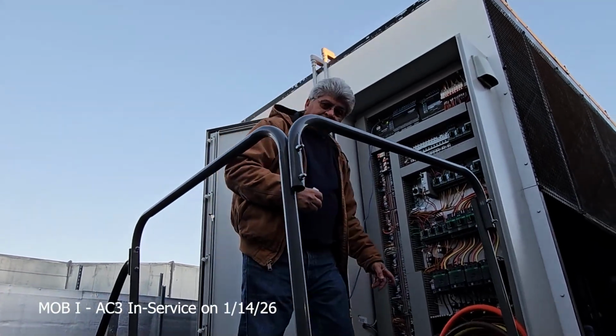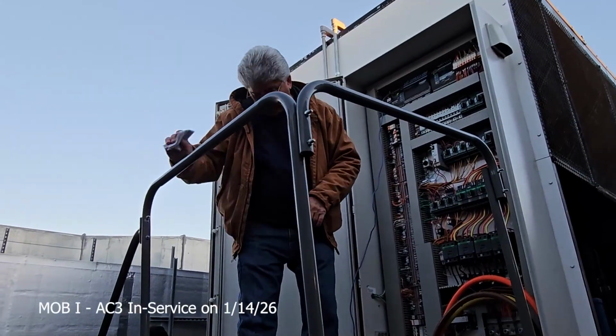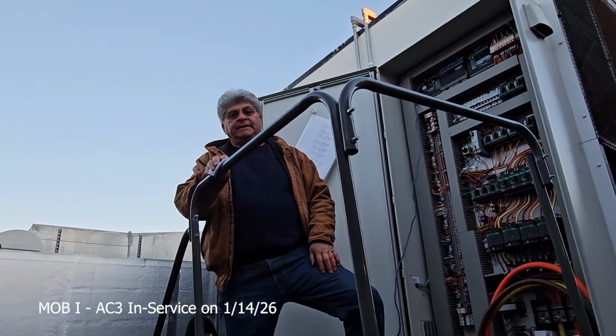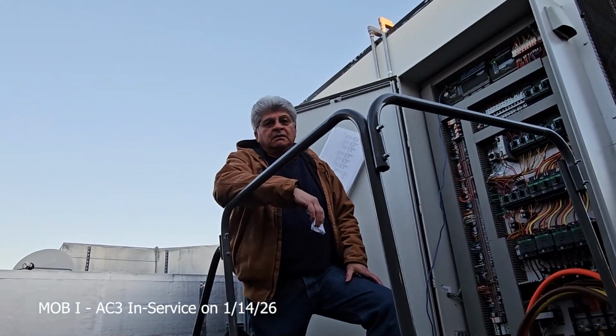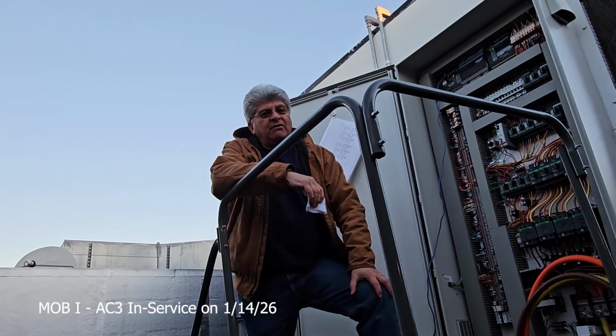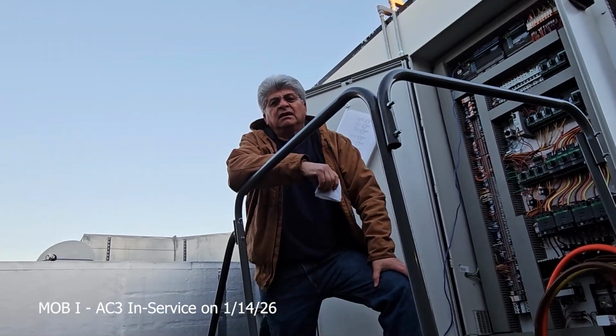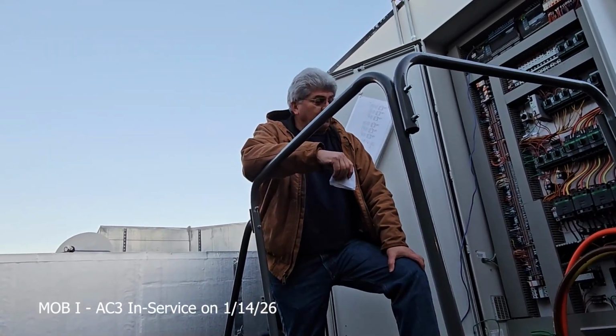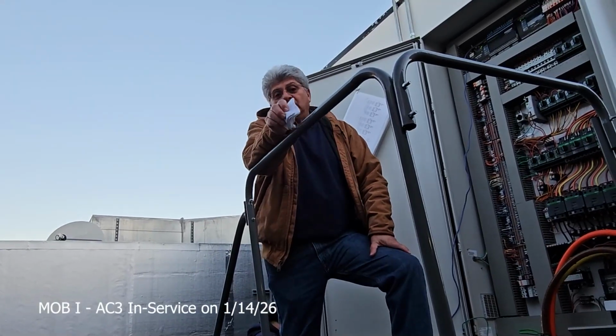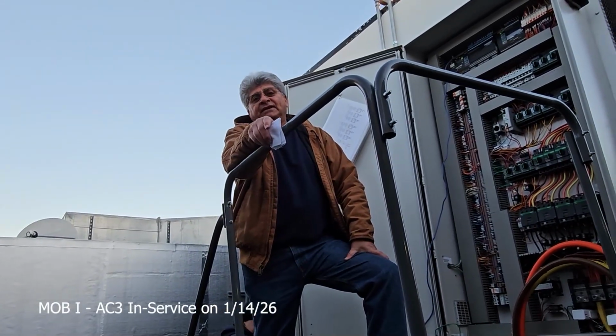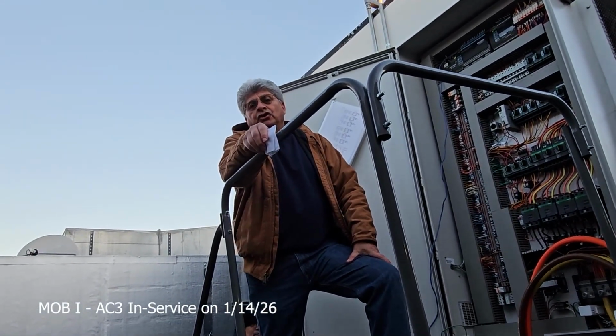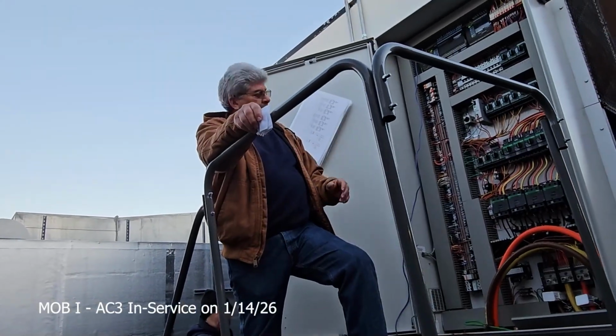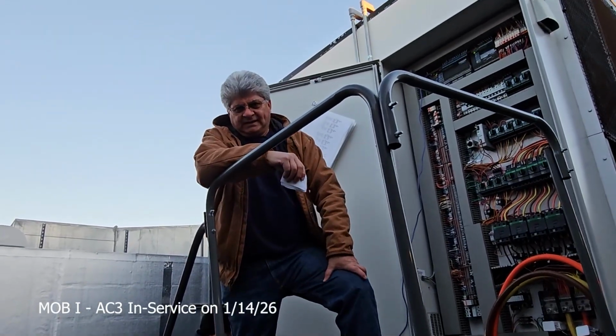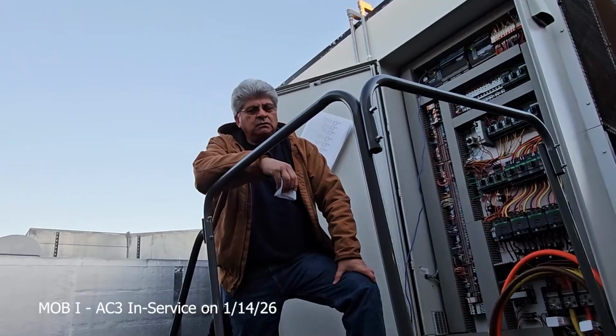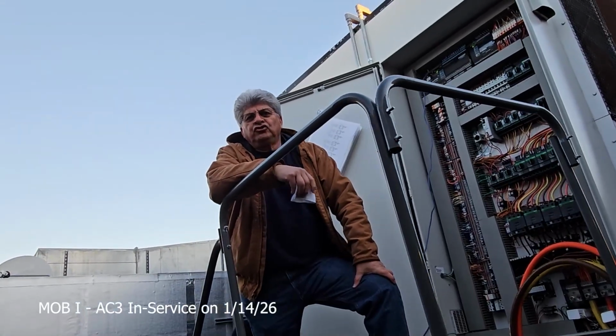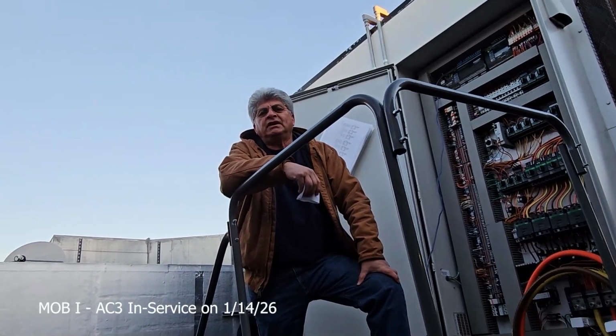Does it have the Delta P alarm trip? I'm not a smart guy. What's a Delta P? The filter dirty. Oh, static pressure alarm. Yeah, static. That's it. You're going to have that downstairs on your front end if you have it. It's not local, so it does not trip the unit. No. Okay. Do you want the unit to shut down because your filters are dirty?